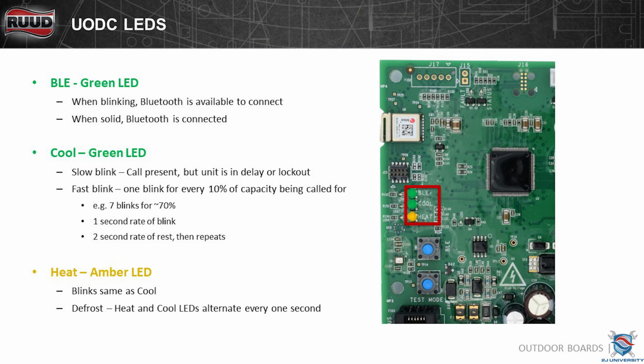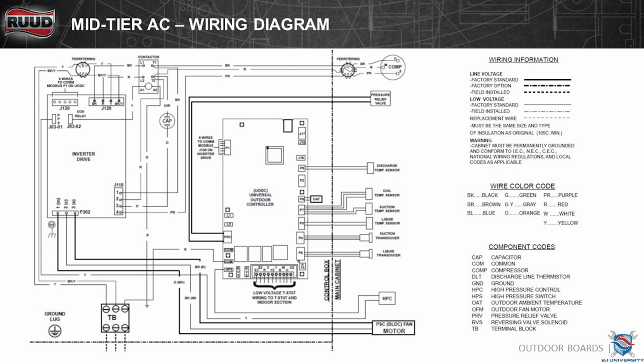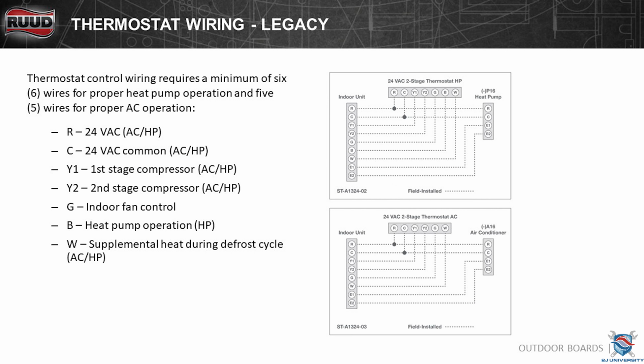So it does have some LEDs on it. Once again, I always recommend connecting to your Contractor app and seeing what that thing's doing. The LEDs are pretty vague. It's just going to tell you really if it's in heat or cool and if it's communicating. A little bit on the wiring. Once again, on the low voltage, E1, E2, R, and C are the only things that are active on the mid-tier boards. Same thing, 4-wire connectivity, outdoor unit. Hopefully you guys are seeing kind of a common theme here. UP16, UA16, RA15, 4-wire connectivity, indoor and outdoor.